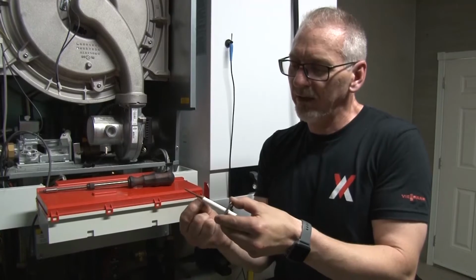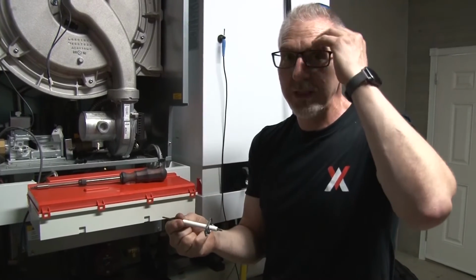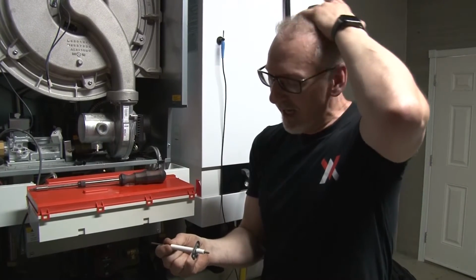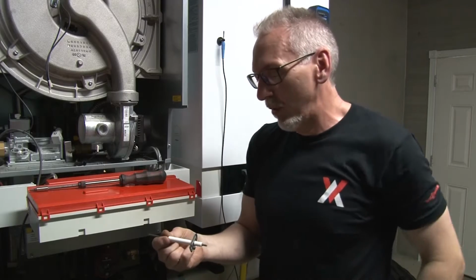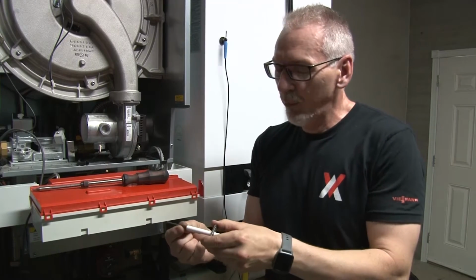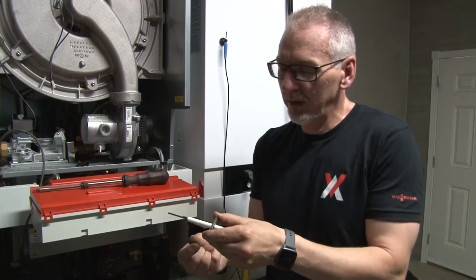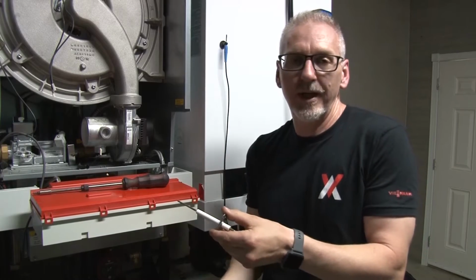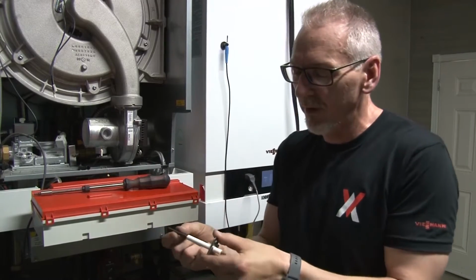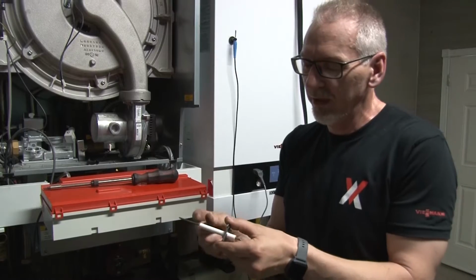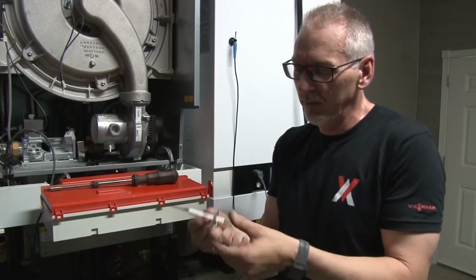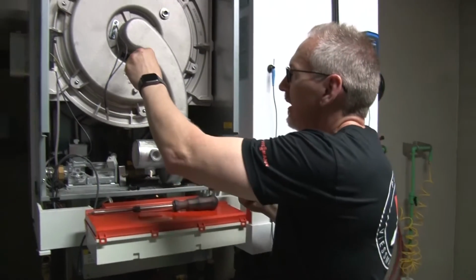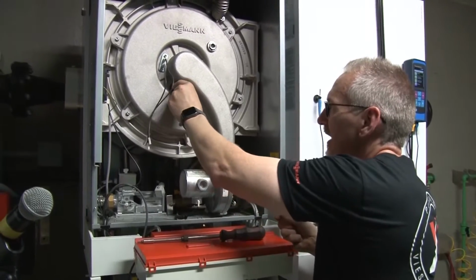And when you're dealing with things like low gas pressures and stuff like that, which we can't control as the manufacturer, but they're within spec of the boiler, this will pick up weaker flame signals a little bit better, a bit more conductivity, and we have a little less issues as far as EE and EB faults. So this would be the new style electrode that you'll end up getting. So if you have the older one and you want to replace it, you might end up with this particular one.